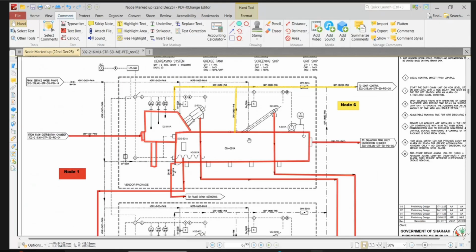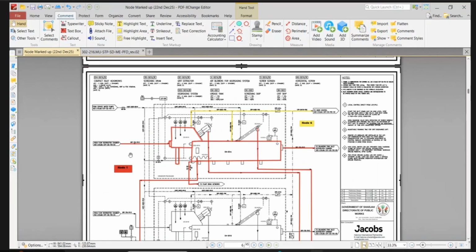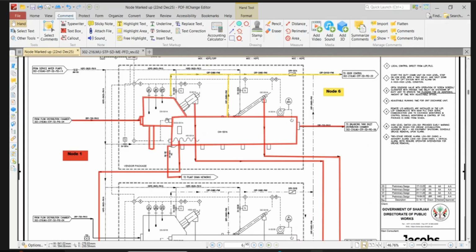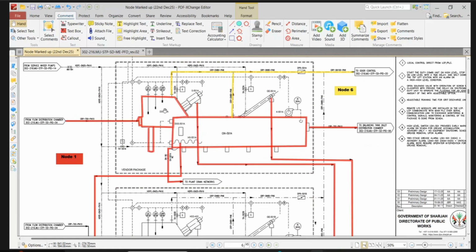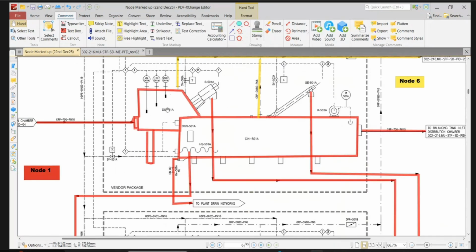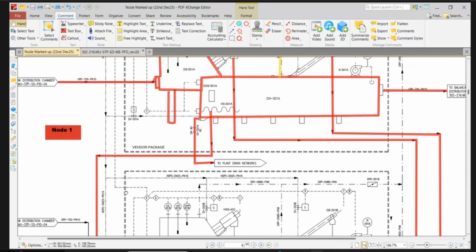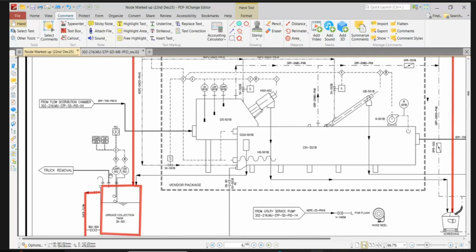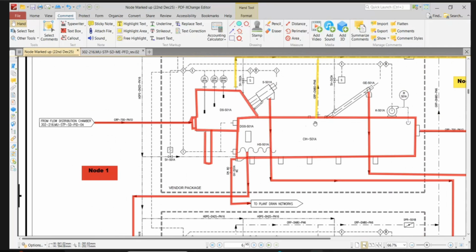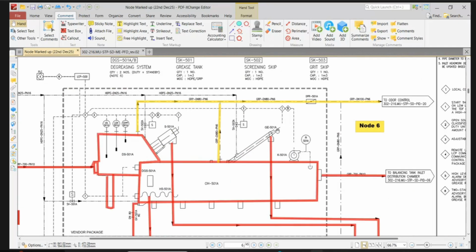Okay, guys, before we go for the tea break, please explain what is done. In this P&ID, we have taken all the causes of no flow and high level here. We have taken high level, and if this screw is stopped, we have taken that, and we have taken high level here because the LSHH is here, and we have also considered this GE501A.